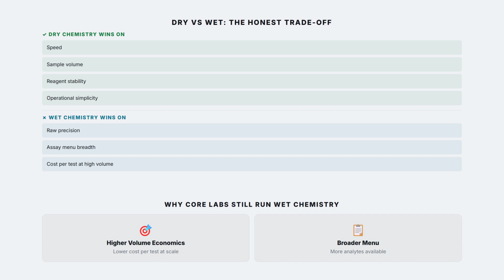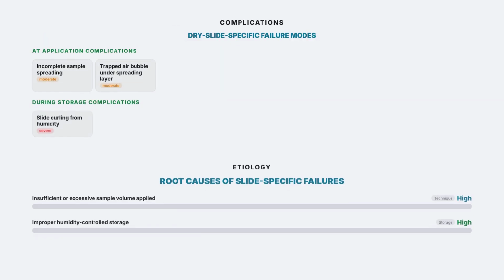The failure modes are worth knowing cold, because they're specific to this technology and won't show up in generic wet chemistry troubleshooting training. Incomplete sample spreading leaving dry patches on the reactive area, air bubbles trapped beneath the spreading layer blocking migration, and slide curling from improper storage humidity distorting the optical reading geometry entirely. A full technical scenario, not a patient one.